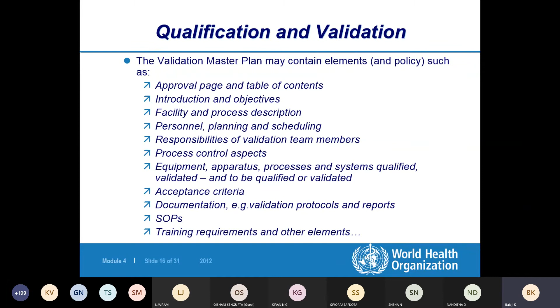Acceptance criteria is very important - any validation strategy applied should have a defined acceptance criteria. Documentation requirements, validation protocol and report requirements, SOPs, training requirements, and during execution you may have incidents, deviations, or change control requirements - how you follow these quality systems should all be well written in the validation master plan.